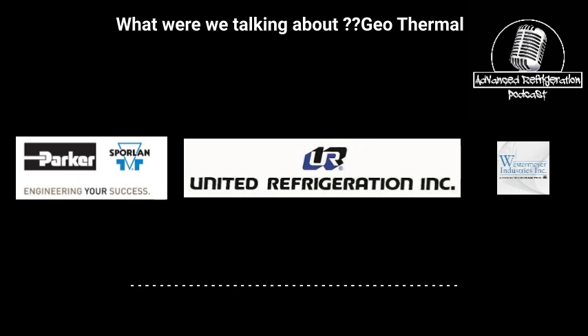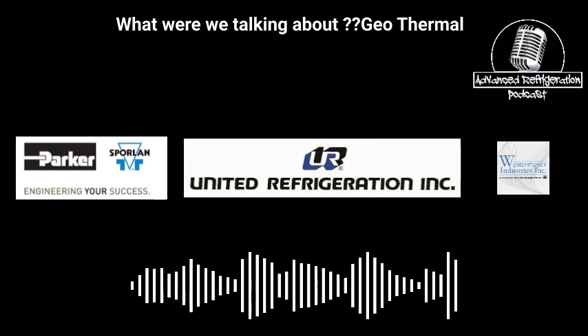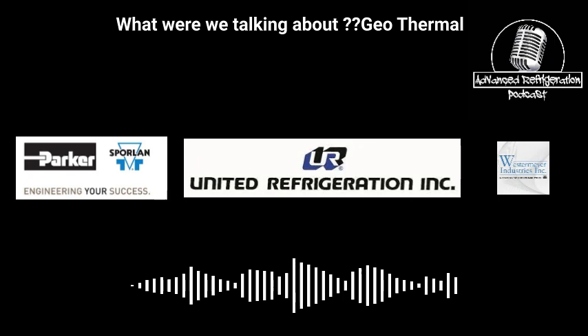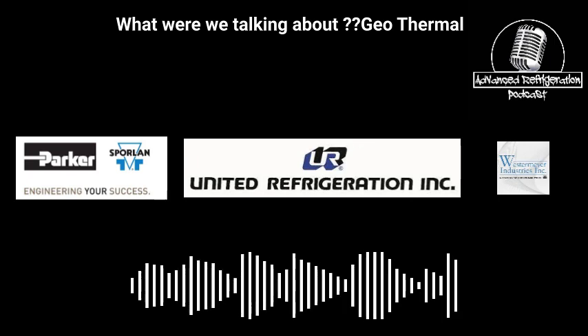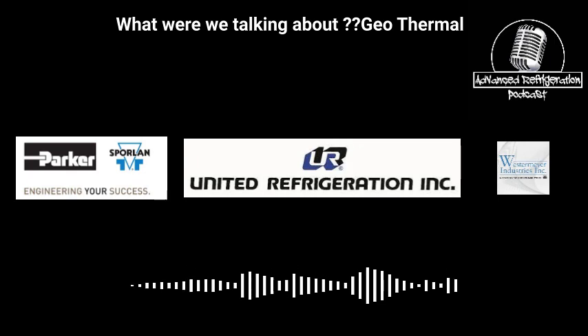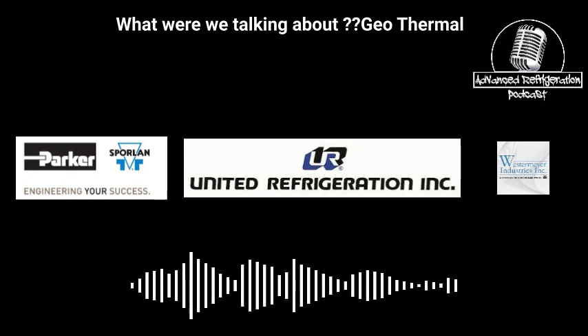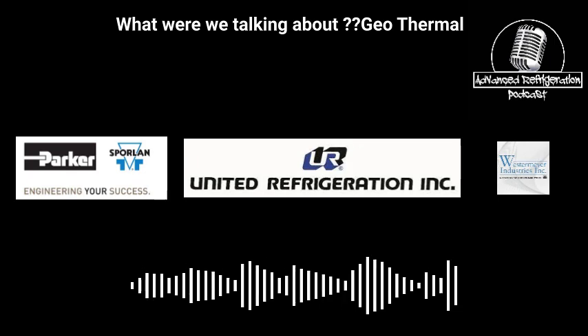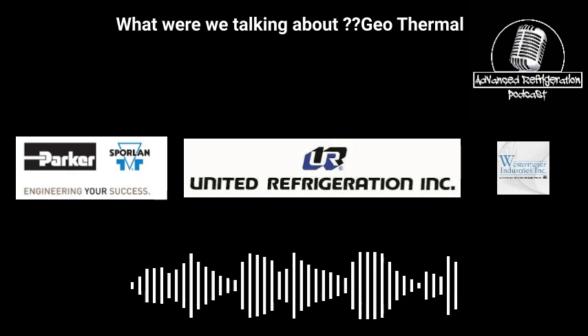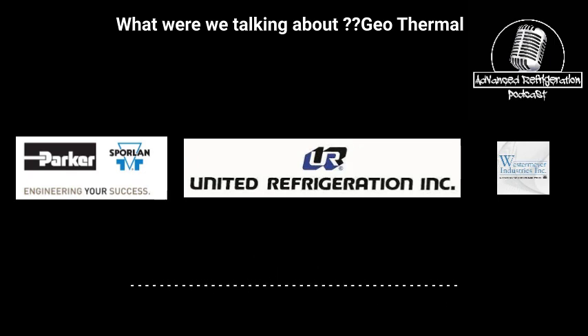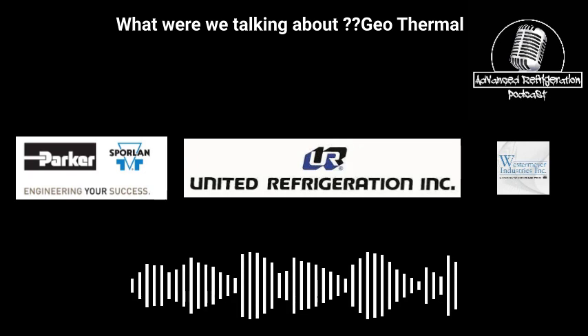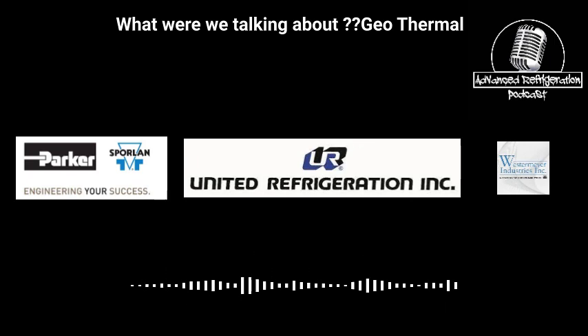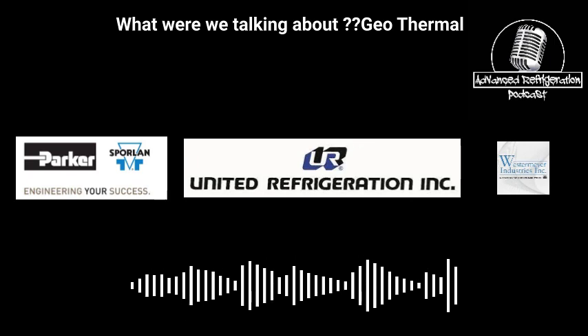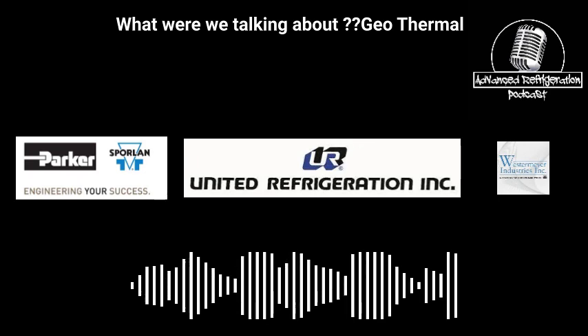Oh shit! Because they just pull all the heat out of it, and then there's 60 tons of heat pump in that unit too that are pulling it out. So, I mean, they're almost as much load as the rack. Oh shit! So that's wow. So generally, we have to shut those things down. We have to shut the heat pumps down in the wintertime for those, and then they just run off gas heat.